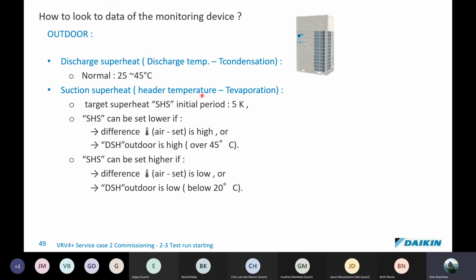Suction superheat is the header temperature minus the temperature of evaporation that we measure on the suction gas side of our manifold, and the target superheat is set to 5K. But suction superheat can be set lower if the difference between the air and the set point is high, or the discharge superheat outdoor is high, over 45 degrees. Then it will try and set down the suction superheat. Suction superheat can be set higher if the difference between the air temperature and the set point is low. So basically here we're increasing the suction superheat, or the discharge superheat outdoor is low, below 20 degrees.